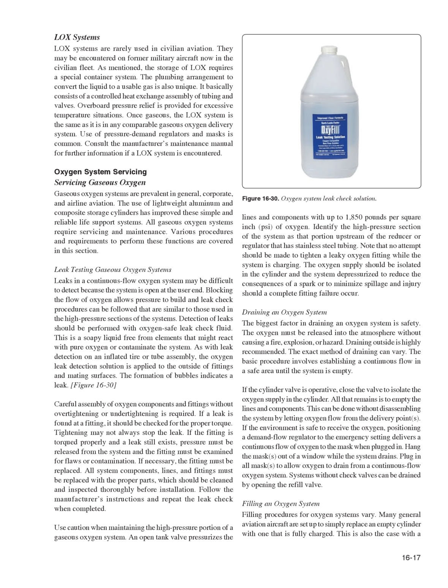All system components, lines, and fittings must be replaced with the proper parts, which should be cleaned and inspected thoroughly before installation. Follow the manufacturer's instructions and repeat the leak check when completed. Use caution when maintaining the high-pressure portion of a gaseous oxygen system. An open tank valve pressurizes the lines and components with up to 1,850 psi of oxygen. Identify the high-pressure section of the system as that portion upstream of the reducer or regulator that has stainless steel tubing. Note that no attempt should be made to tighten a leaky oxygen fitting while the system is charging.